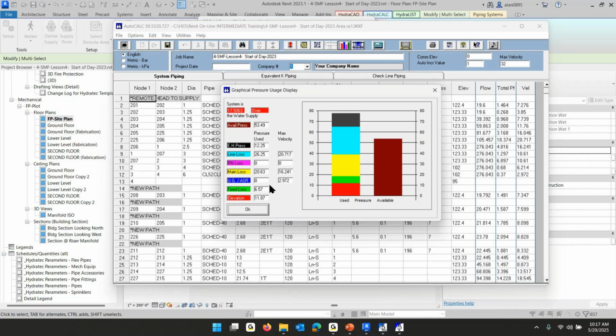So the usual approach is, I'm over the curve, make the pipe size bigger. And I think that's a part of our process. And I think the 1.25" lines are probably my first target. And I see I've got 2.5 in the mains also, left over from, we said, we got plenty to use. Let's make the mains 2.5. I might put that back to 3-inch.